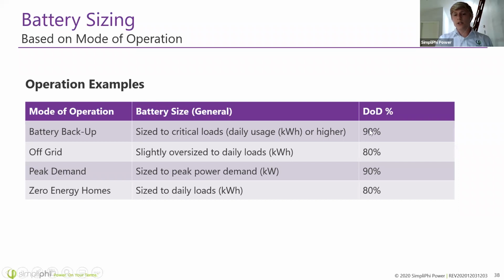Now if you're just using these batteries as backup for a grid-tied system, only coming on during a power outage, you can get away with 90% depth of discharge, maybe even 100 if you want to push it.